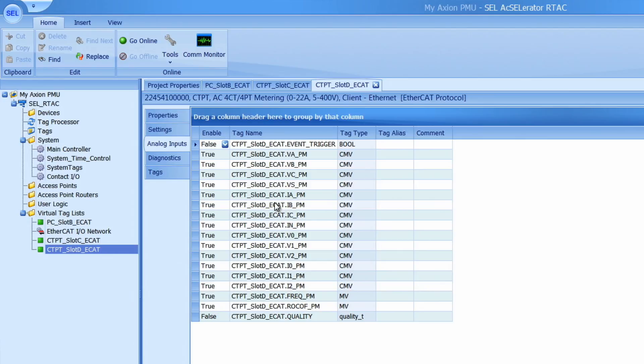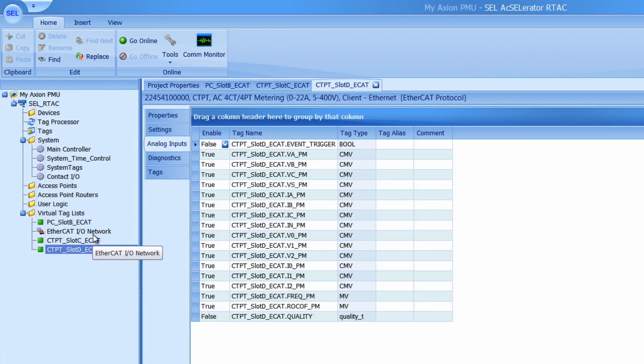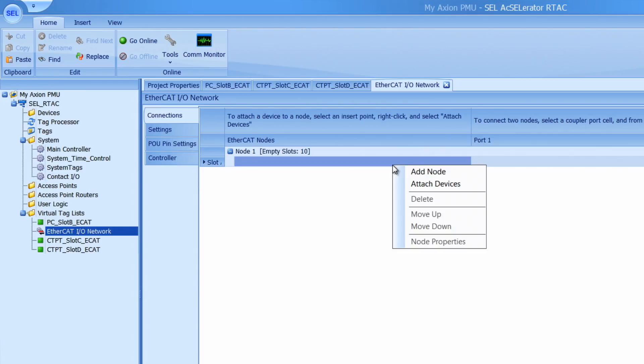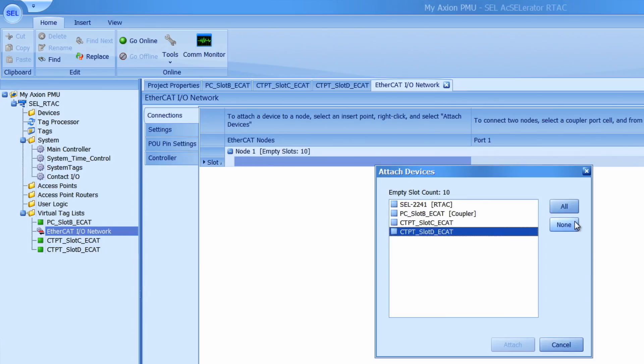Now that all our devices have been added to the project our next step is to configure our EtherCAT IO network. I can select on this in the project view and go to the connections tab first. I can add in all my devices into my EtherCAT network by simply right clicking and go to attach devices and I'll select all.